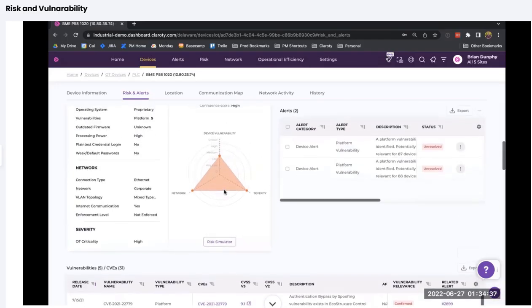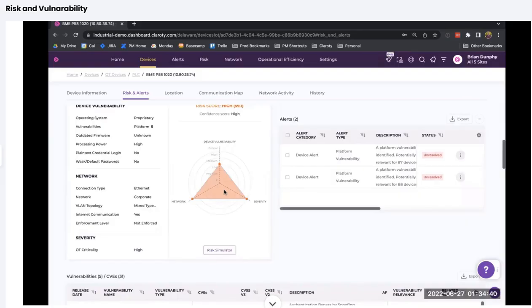And the reality is that you can have a very high CVSS score of 9 or 10. It may affect a particular asset in your environment that's buried behind multiple defenses, has no internet communications, and the net result is it could be not exploitable at all. Whereas you could have a lower CVSS score of a 6 on a host that is level 3.5, exposed potentially to the internet, far more important for you to handle and resolve that particular vulnerability, even though it has a lower CVSS score.